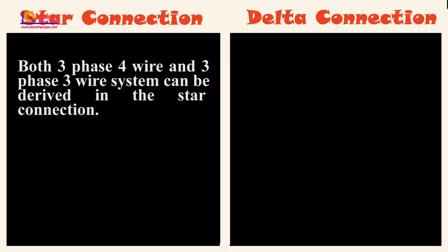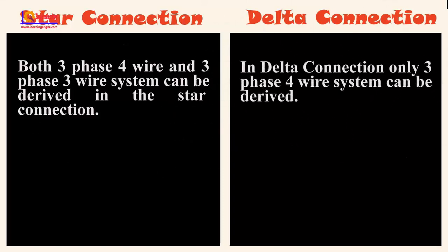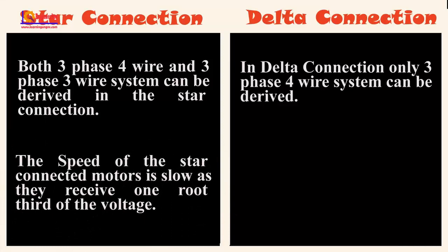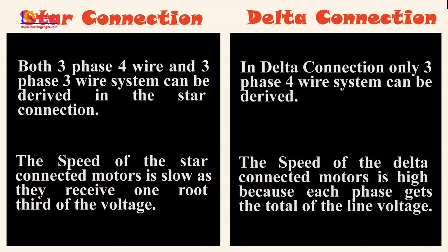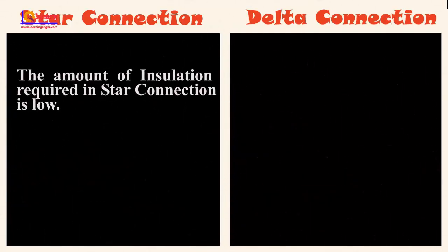Both three-phase four-wire and three-phase three-wire systems can be derived in the star connection. In delta connection, only a three-phase three-wire system can be derived. The speed of the star-connected motor is slow as it receives one over root 3 of the voltage; the speed of the delta-connected motor is high because each phase gets the total line voltage.